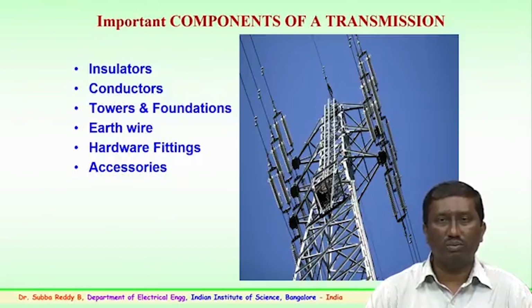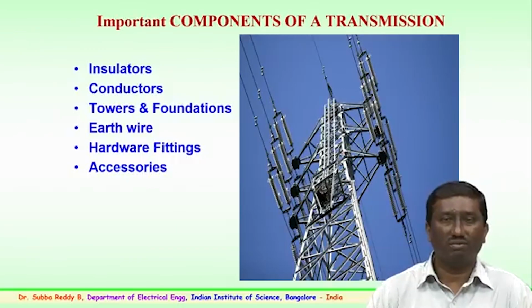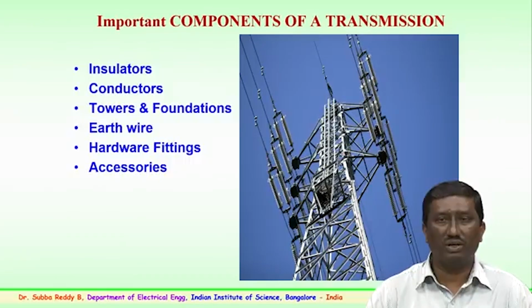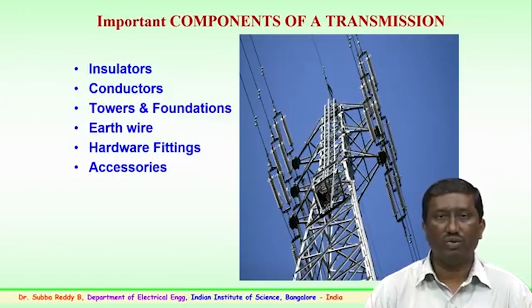The third, and a much more important component, is the towers. Without towers, the conductors and insulators cannot be used. So, the tower is one of the important components of UHV or EHV transmission systems, and apart from towers, there is the foundation, what type of foundation is being used for the towers. This again depends on the area where the tower is being erected, either in a hilly area, or in normal plain conditions, or at high altitudes.